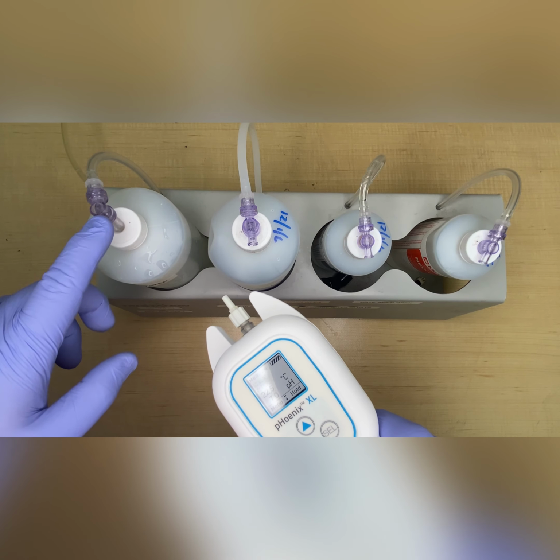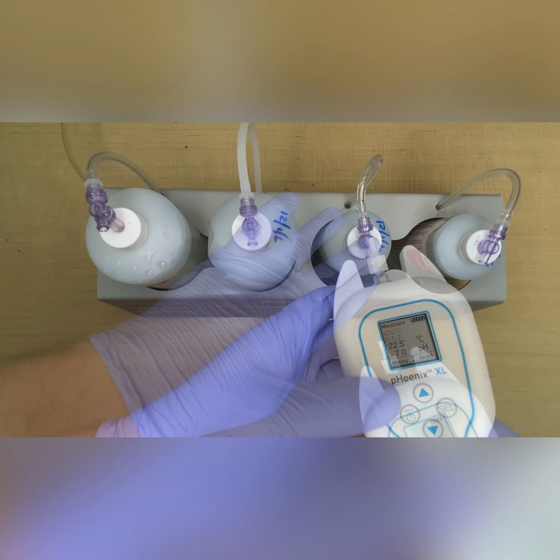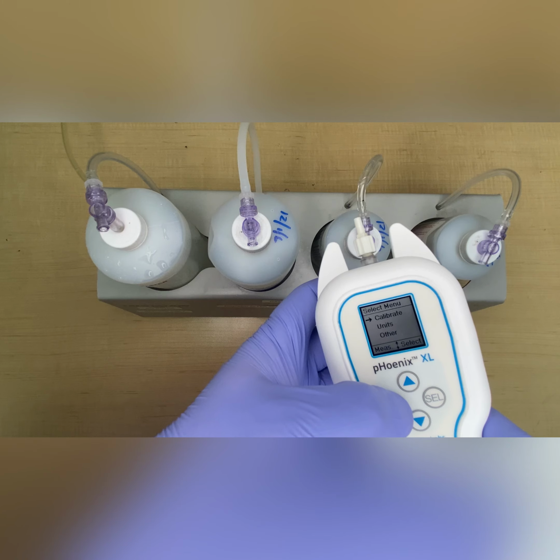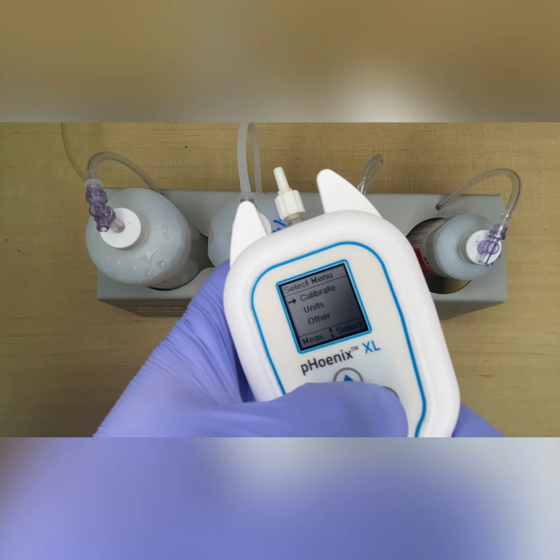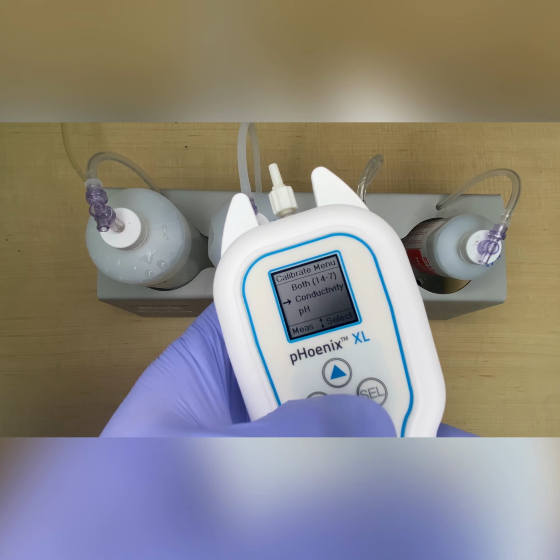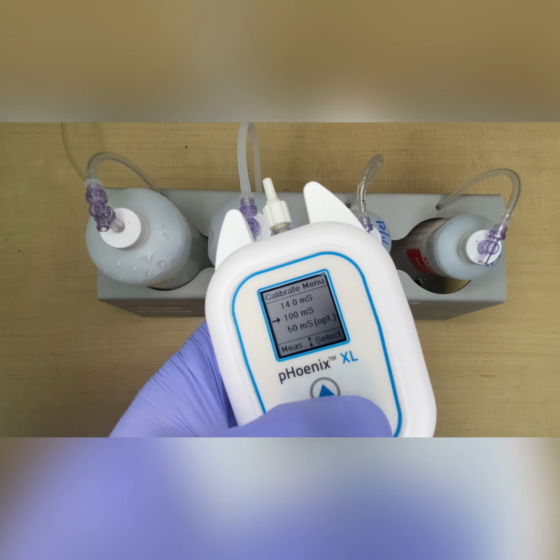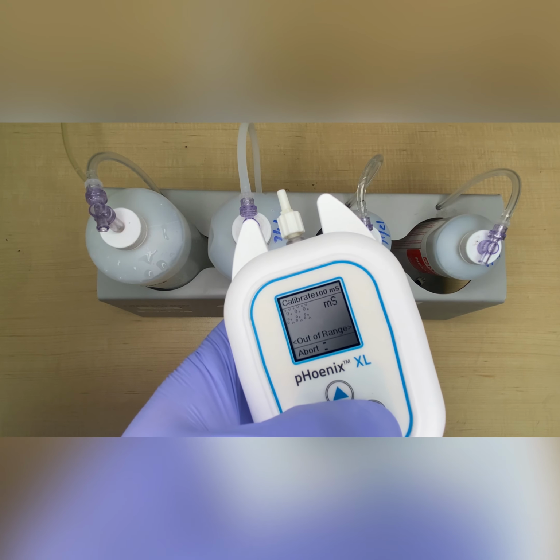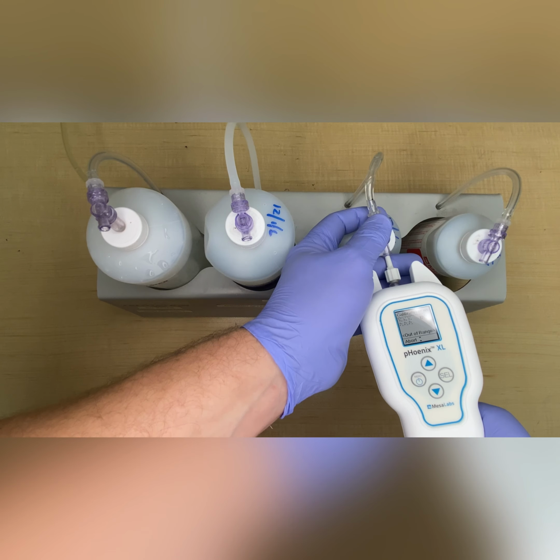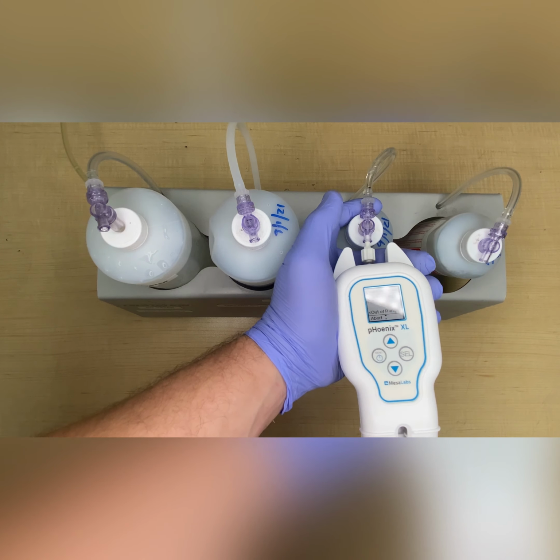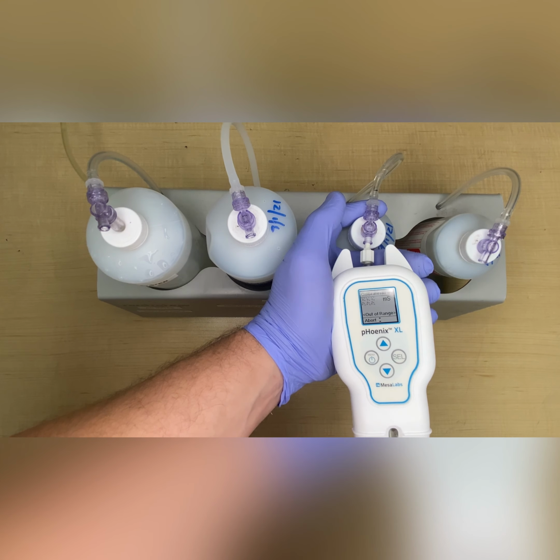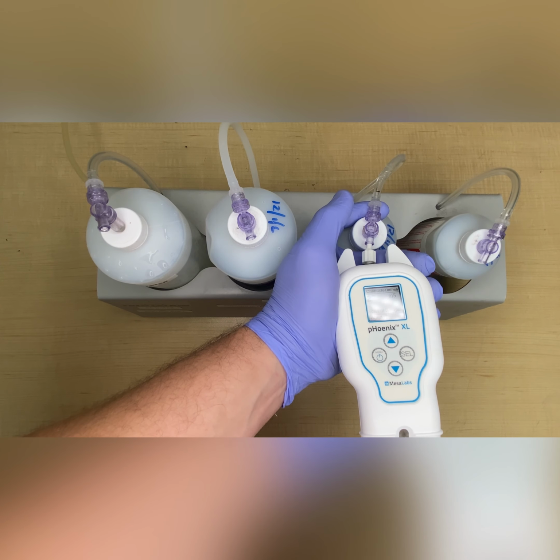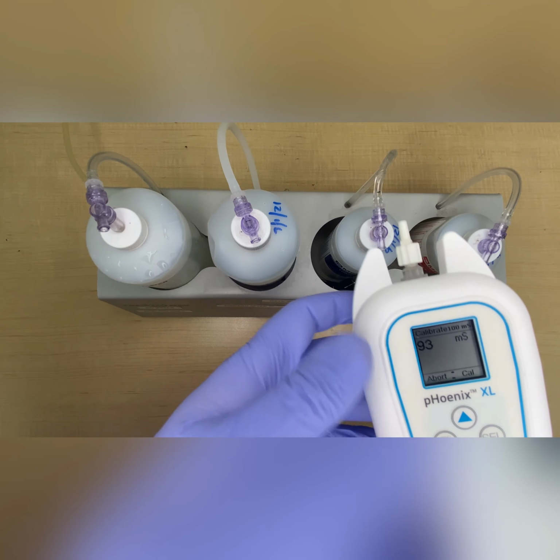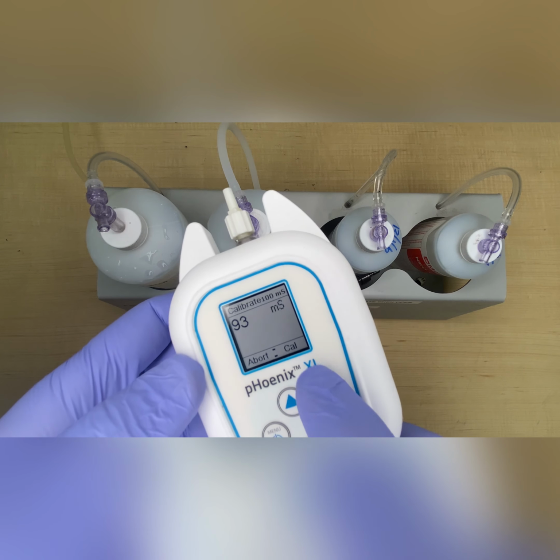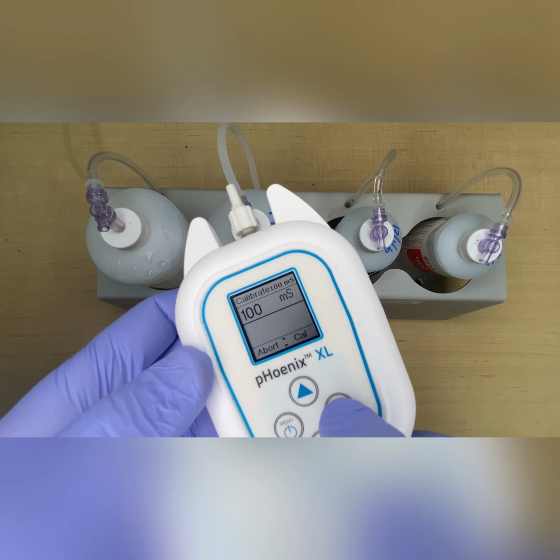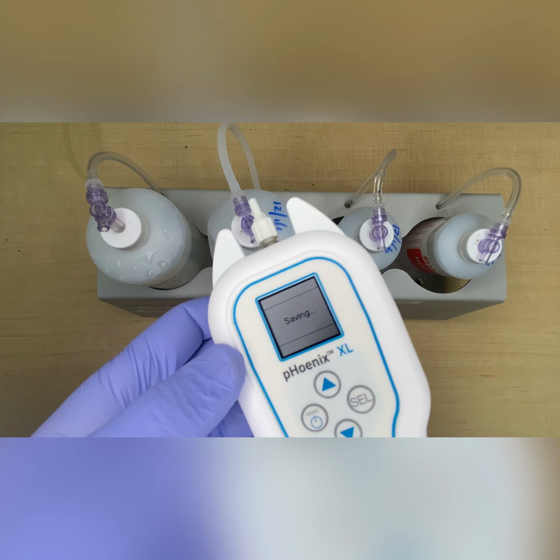Next up, make sure before moving on to your 100 solution that you rinse your meter out with the RO water. So we're going to go back in to menu. We're going to come down to conductivity and select high, and we're going to go down to the 100 and hit select. We're going to go ahead and pull up our 100 solution. You're going to do the same thing. You're going to flush out your meter a couple of times with the solution, and then make sure you've got your cal key down at the bottom and go ahead and hit select. And that's going to save that calibration for the 100.